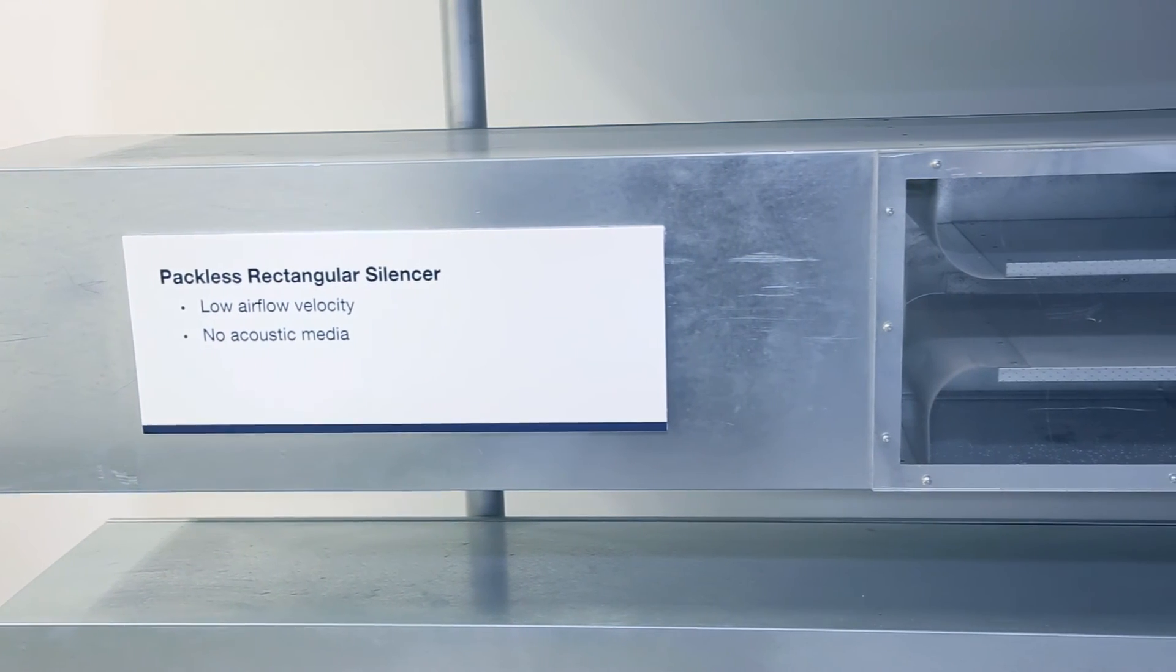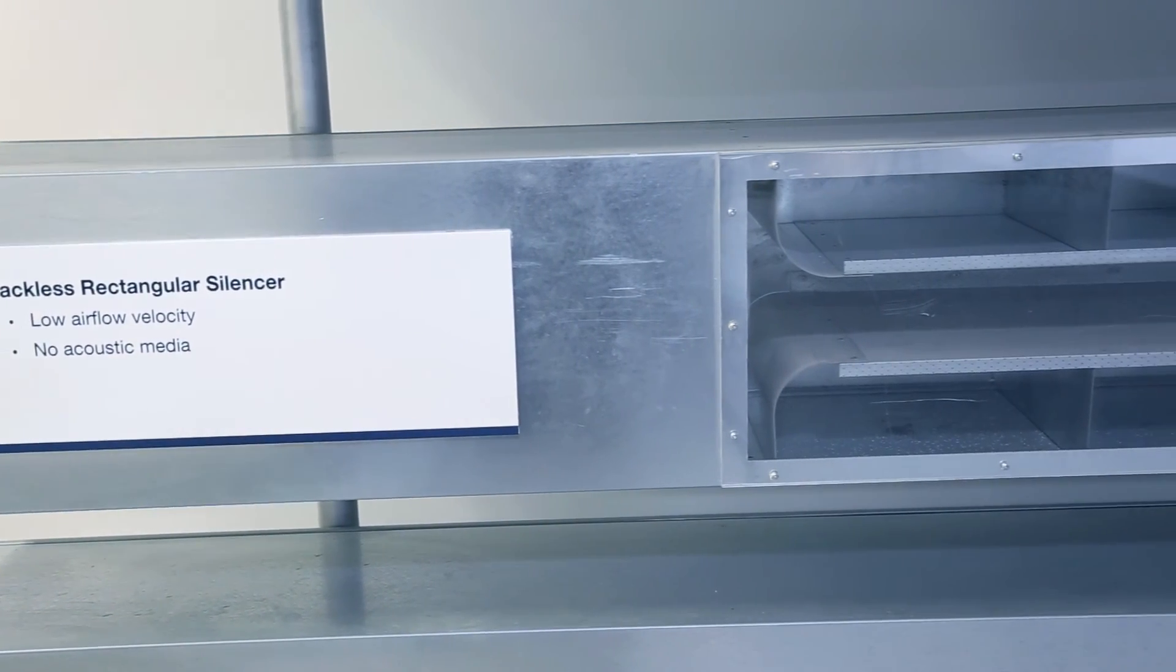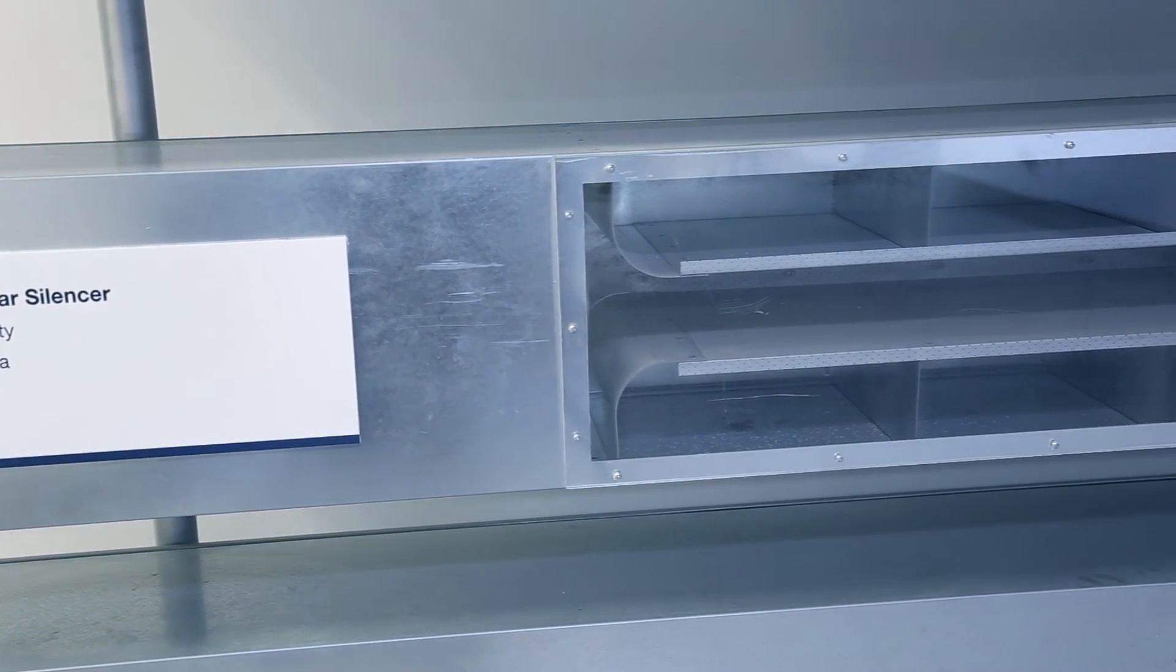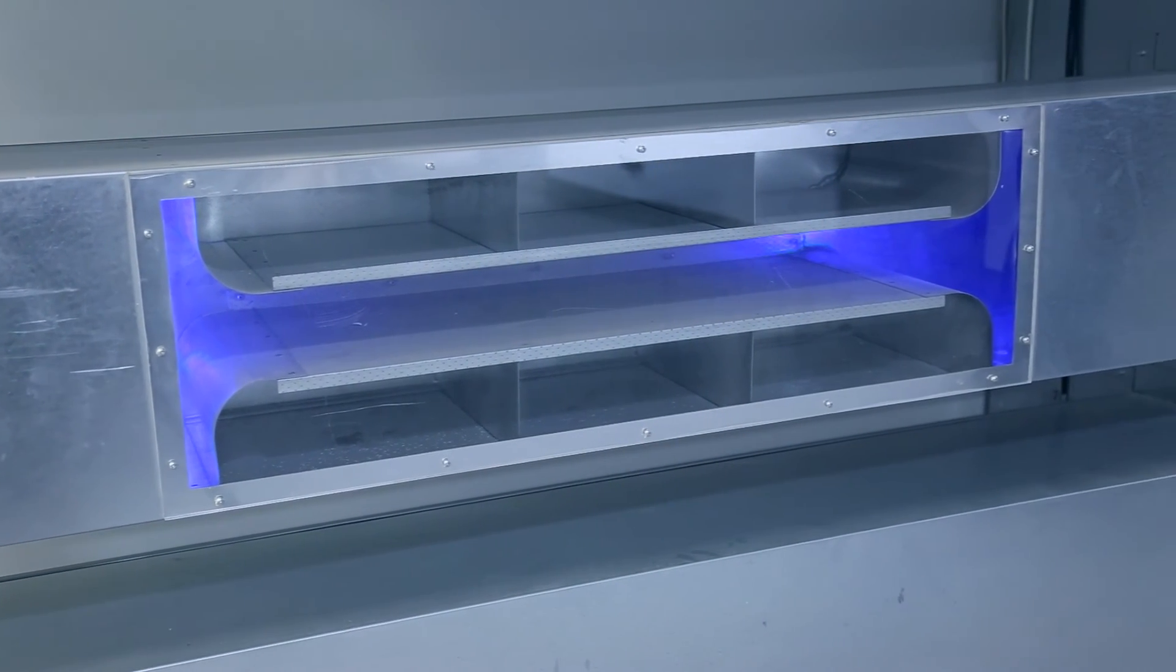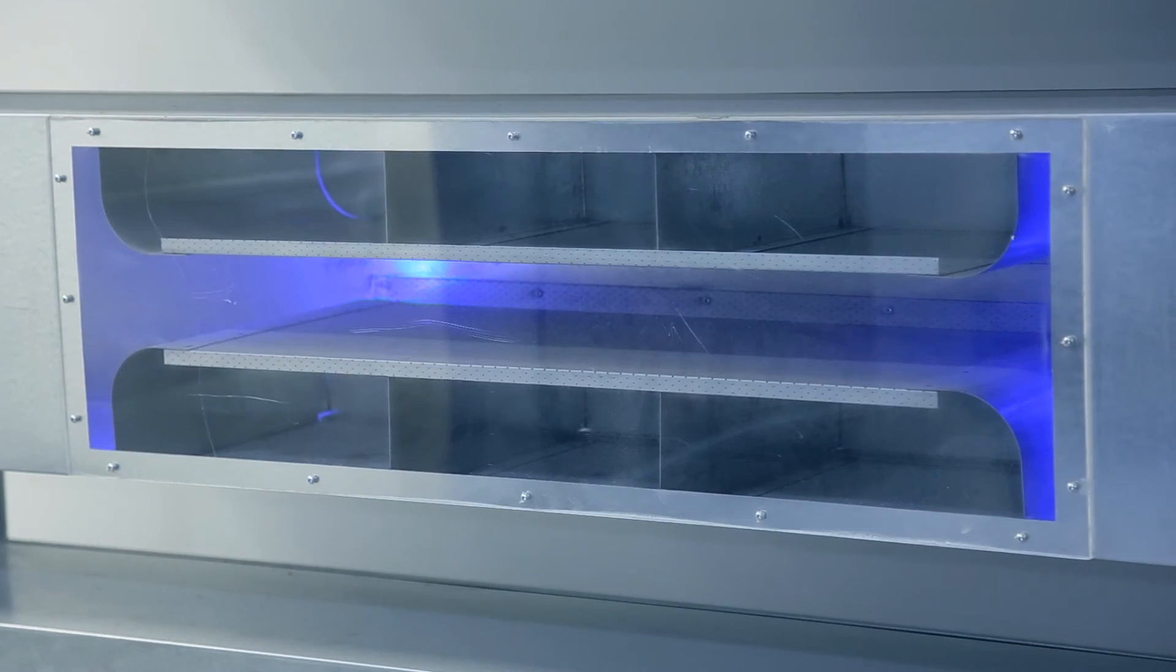The final silencer in our test system is a packless rectangular or no media silencer. As you can see this packless silencer has a similar baffle configuration to the RL silencer and the pressure drop measured is similar.